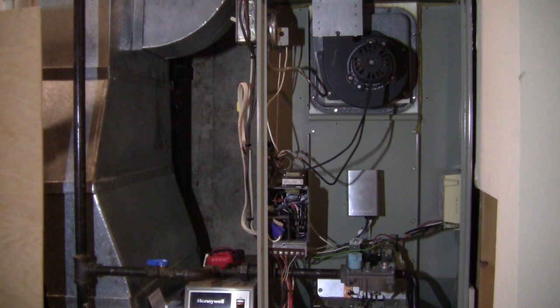So what situation can cause the burning air to leak to the living area? Sure, we already know the first one is this fan. This fan has to run. This fan has to build up vacuum inside the chamber, and this vacuum will be detected by this pressure switch. With this working, and we know this fan is working, this fan will suck up the burning air from here. Okay, this is for the burning air.